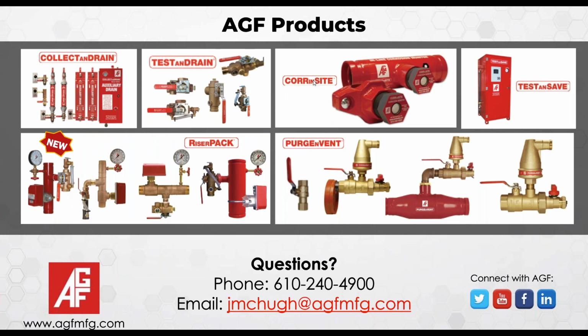So how we see customers utilizing this is they are putting them right at their inbound water supply, and then they're putting them in some strategic locations that are visible around the property. And then during their annual inspection, they just write down a note that if it is still indicating as clear, or if it has turned bright orange. So if it has turned bright orange, then there's little instructions written on the side of the unit that tells you that you've lost a third of the wall of your pipe.